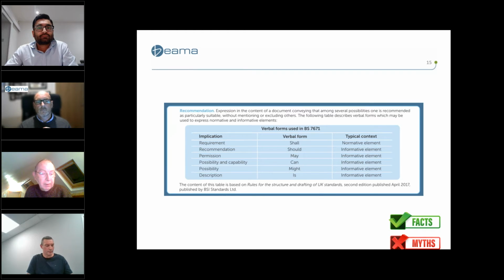In the case of Regulation 421.1.7, covering the requirements for AFDDs, two terms are used: shall and recommended. Shall is pretty self-explanatory, it's a requirement, it must be done, it must be covered. Recommendation, in the definitions within 7671, is described as an expression conveying that among several possibilities, one is recommended as particularly suitable without mentioning or excluding the others. So what it's saying is, where there may be options to meet the requirements of the regulation, the stated recommendation is particularly suitable.